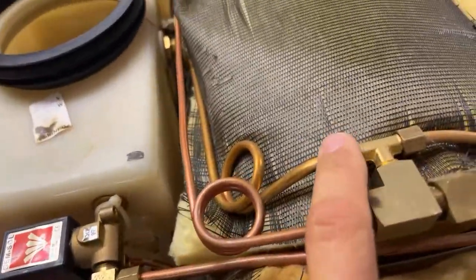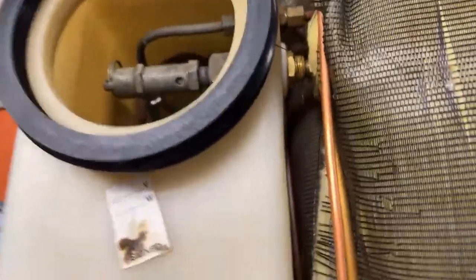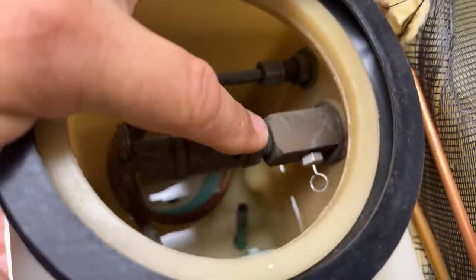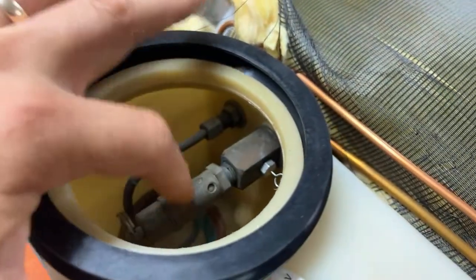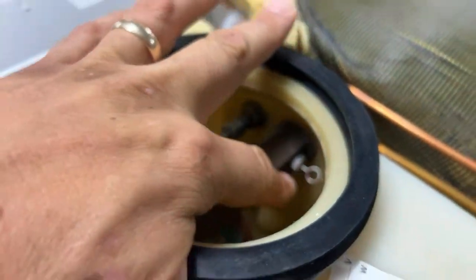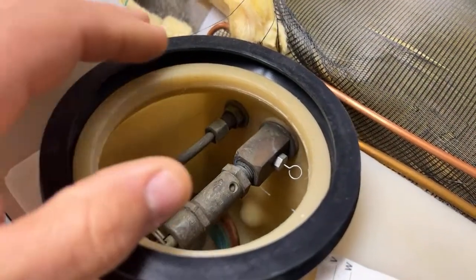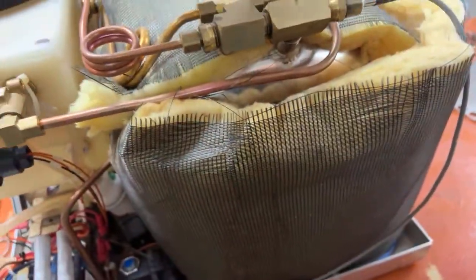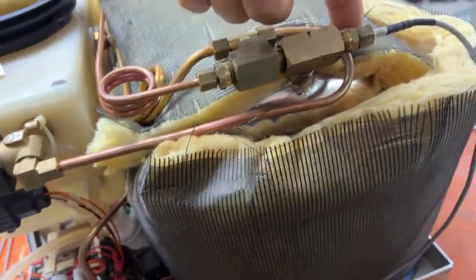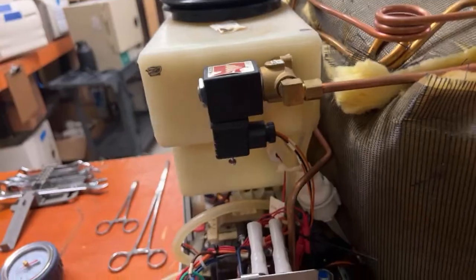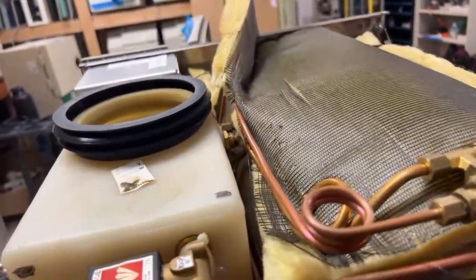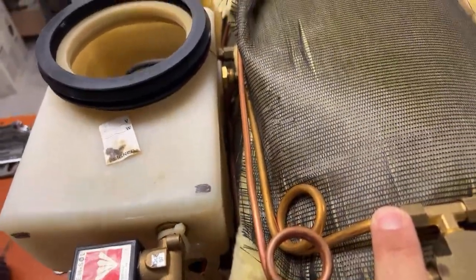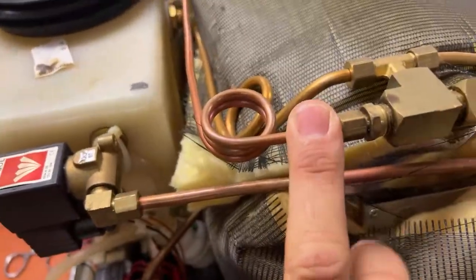And then this one right here is going forward, and this bigger pipe goes into the reservoir. That's for your safety valve, and that's also a little air vent valve that has a little pin on it that you pull. And then there's another port that comes over here to our solenoids, and this is what controls the venting. And right here again is where we're going to hook our gauge in.